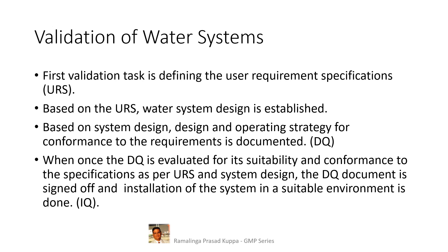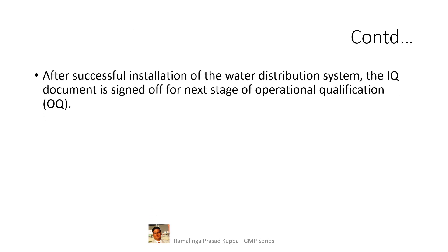IQ is initiated after the DQ document approval is signed off. Installation is done in a well-ventilated, accessible area with adequate space for routine cleaning and maintenance. It is important that the water treatment area is maintained clean and dry at all times, and there should not be any leaks in the entire treatment system or in the transfer lines. It is recommended that there should be access control to the water treatment area. After successful installation of the water distribution system, the IQ document is signed off for the next stage of operational qualification, that is OQ.